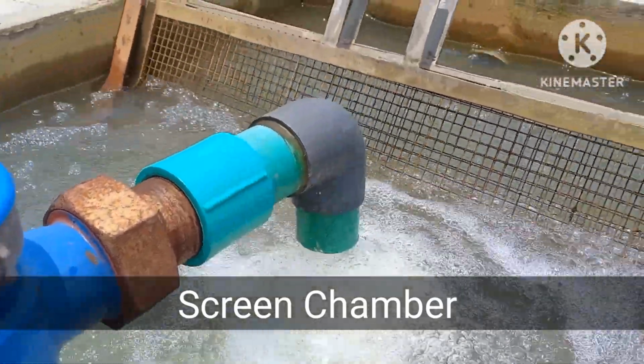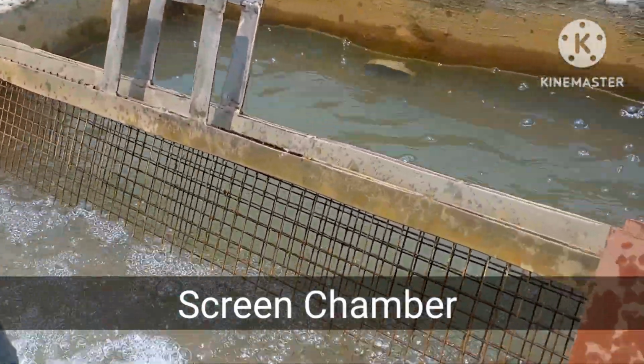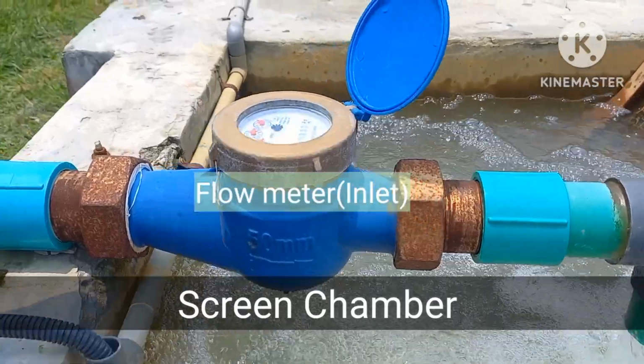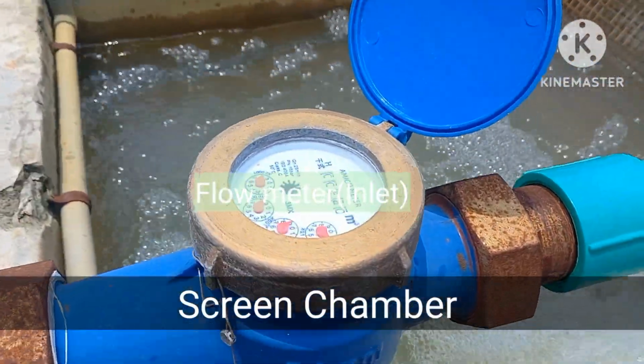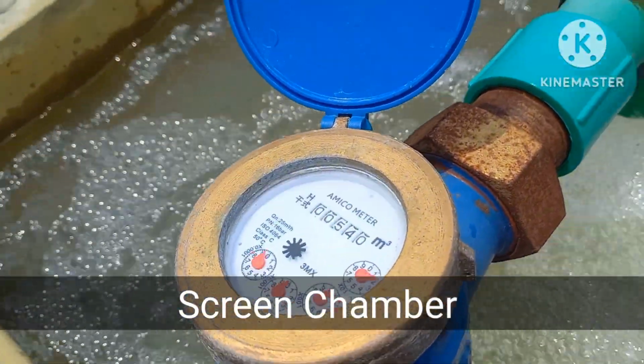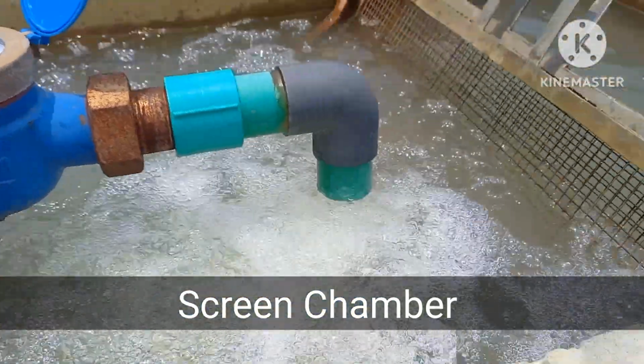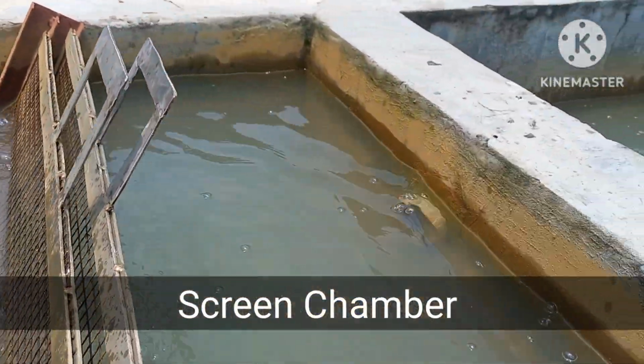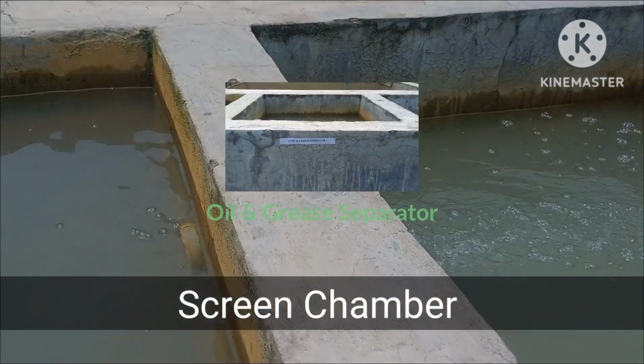The purpose of this screen chamber is to remove larger particles from the effluent, control the flow by reducing hydraulic jump, and enhance the efficiency of effluent transfer pumps.